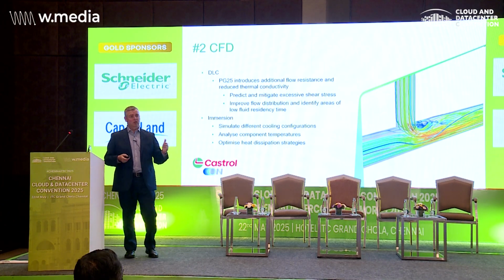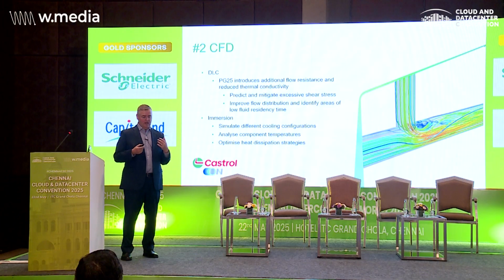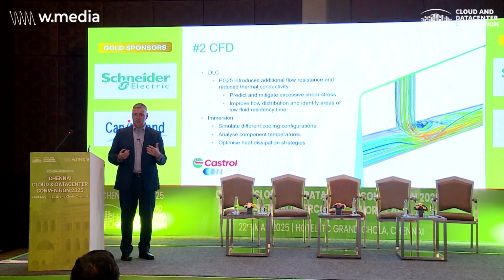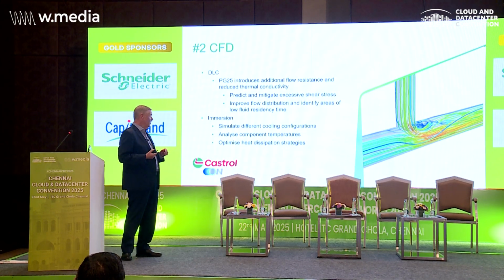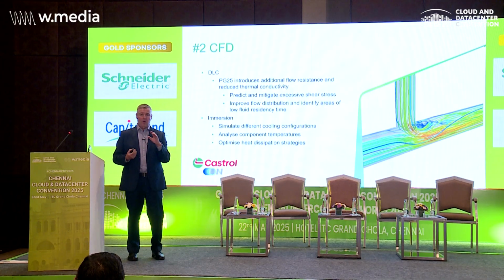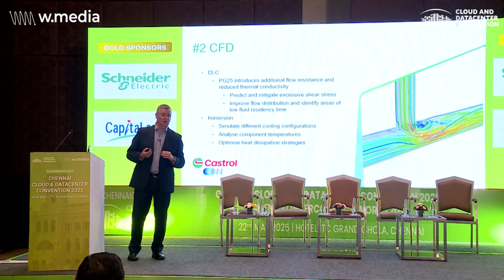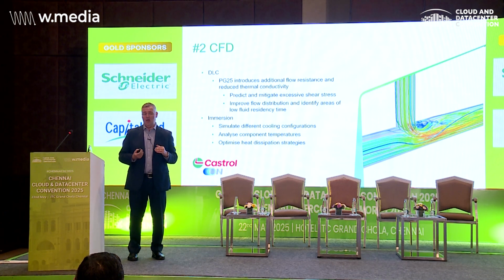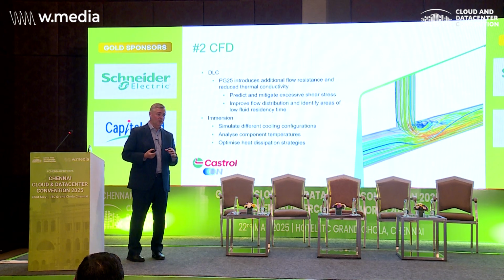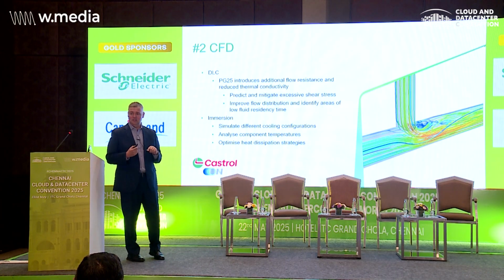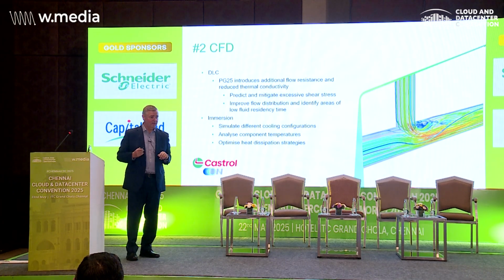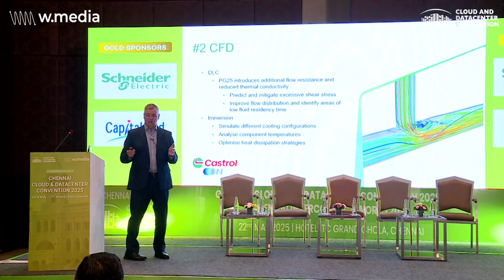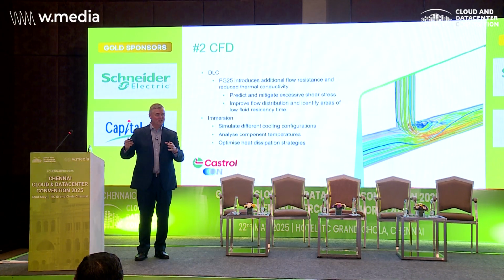Immersion - we can do it as well. We can use it to predict how an immersion tank might work at different performance levels, whether we're driving for performance or for efficiency. So we can run different scenarios. We can also analyze different temperatures of components, such as the GPU. If we want to drive it to the absolute maximum without throttling the GPU, we can simulate that without actually sinking a $350K server. It also enables us to determine, if we haven't got the full tank, where we should position it, and whether we should put blanking plates in like we do with air today.